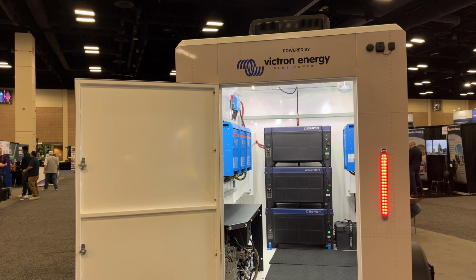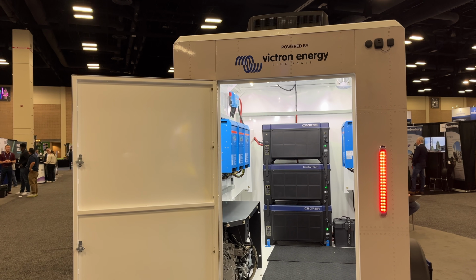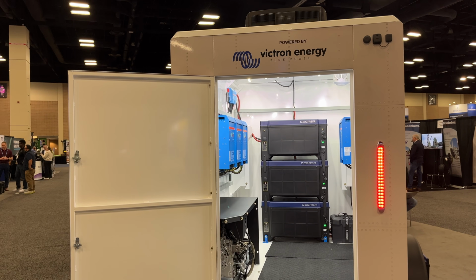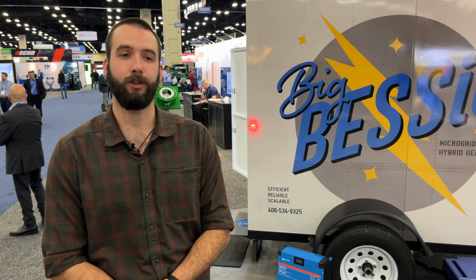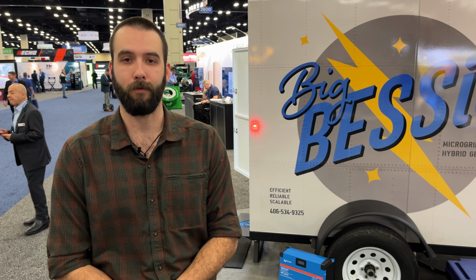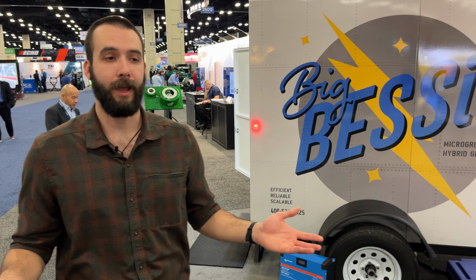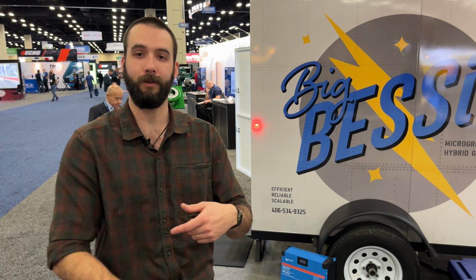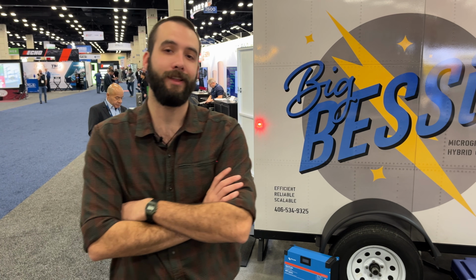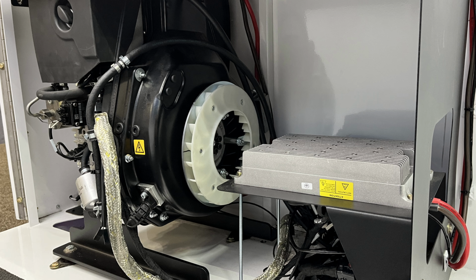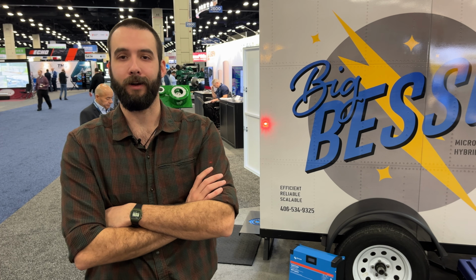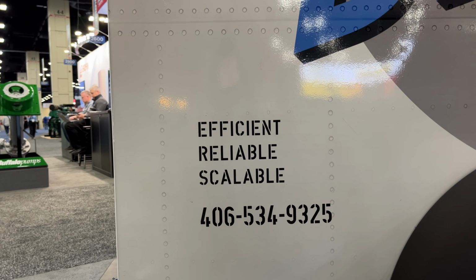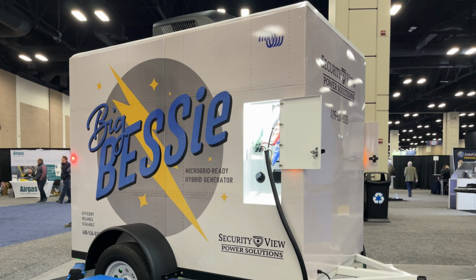And in that circumstance, we would, once again, charge everything onto the batteries, run our load off of the inverters, and then once the batteries hit that state of charge threshold, use a 2-wire remote start to start that existing AC gen set and charge the batteries at the generator's optimal rate. With a setup like this, we could take a 24/7 duty cycle on a regular AC generator and turn that into about 2-3 hours of runtime, running at its most efficient point, saving you all of the costs over the service life of the generator, having technicians come out and service it, oil changes, and just general fuel consumption.